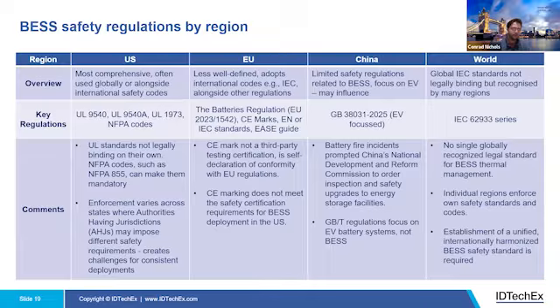The US leads the way for safety regulations and restrictions on BESS thermal management. UL regulations are a framework for battery testing and system thermal management strategies. Several regulations fall under UL 9540, which alone acts as a guideline for deployment. However, NFPA fire codes 855 mandates that UL 9540 certification for all US deployments must be made in participating states. The EU battery regulation, which recently came into force, mandates that all battery systems have a CE mark for sale on the EU market. This shows the product and manufacturer are compliant with EU regulations, but it is not a third-party verification on safety, so it doesn't demonstrate rigorous safety testing and is consequently not valid for BESS deployments in the US.